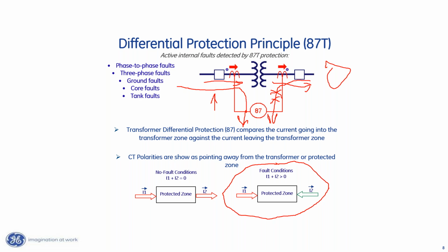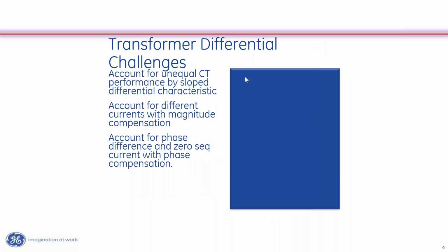The big challenge around differential, though, around all differential, is how do I account for CT performance errors? The challenge is never really to get it to operate for a fault. If it's set right, it operates for a fault. The real challenge around differential is preventing it from misoperating when you have a through fault, a fault outside of the zone of protection. So that's true of all differential. And the real reason that's a challenge is because CTs aren't perfect things. The current transformers that we're using to measure this current and present that current to our relay is not a perfect thing. So let's go back and imagine for a second.